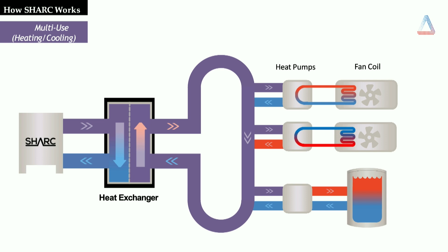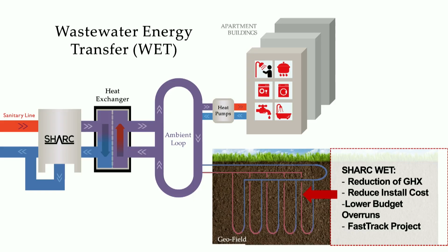If you have a condenser loop across multiple buildings, that becomes an ambient temperature loop, or ATL, and we condition that loop. If a ground heat exchanger is overheating, or you couldn't install enough ground heat exchanger, you simply tie it into the ambient loop. That keeps the temperature swing in the sweet spot range, maximizing the performance and capacity of water source heat pumps, geothermal heat pumps, and water-cooled refrigeration equipment.